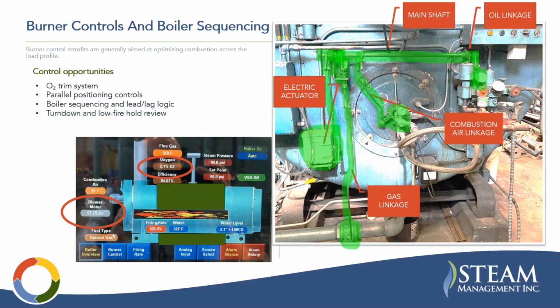The combustion is tuned on this boiler by adjusting these linkages, and it's kind of a manual process. It takes a little bit of expertise, but it is difficult to maintain. It's difficult to tune across all firing ranges and optimize for both fuels. And it quickly gets out of tune as air conditions change with changing seasons. So it's generally recommended to be done quarterly, and that is not always done.